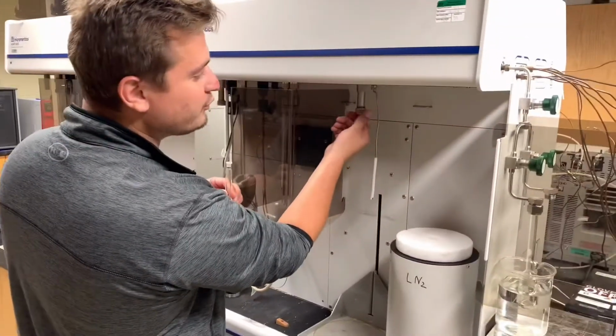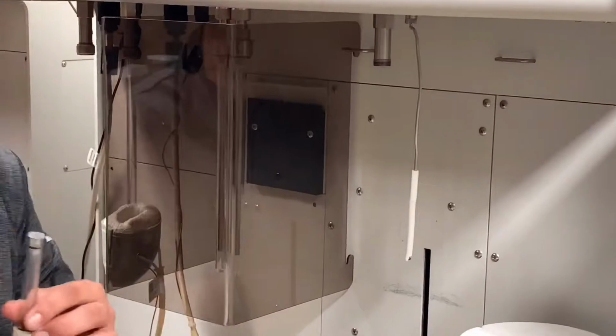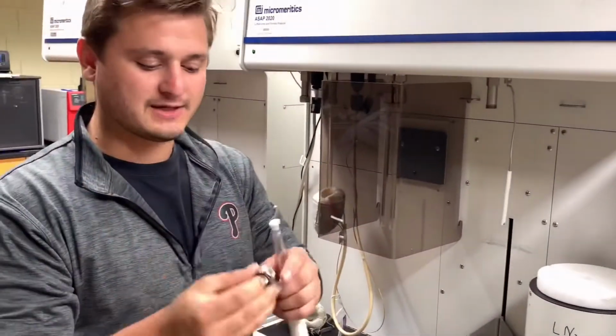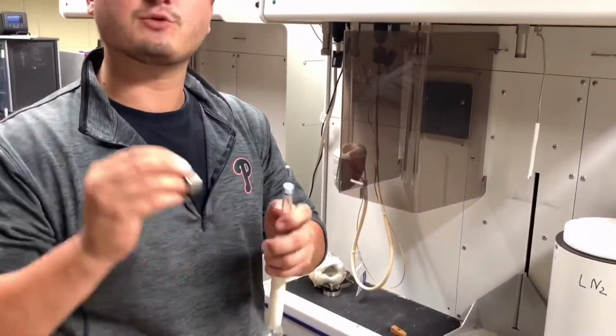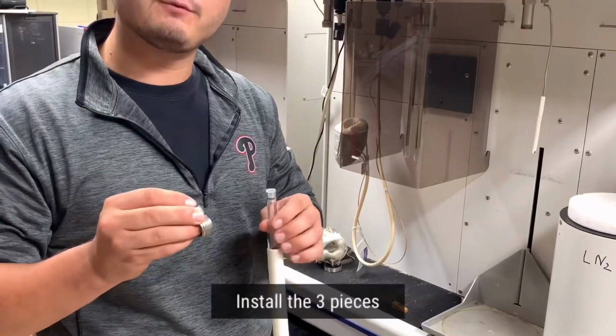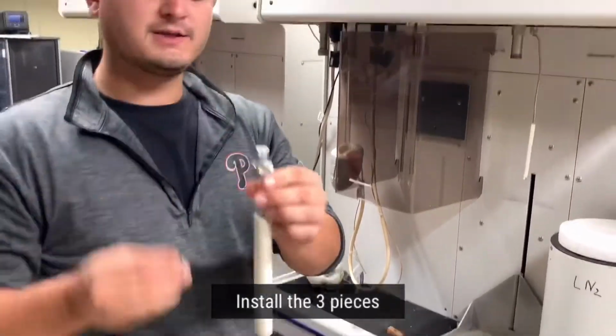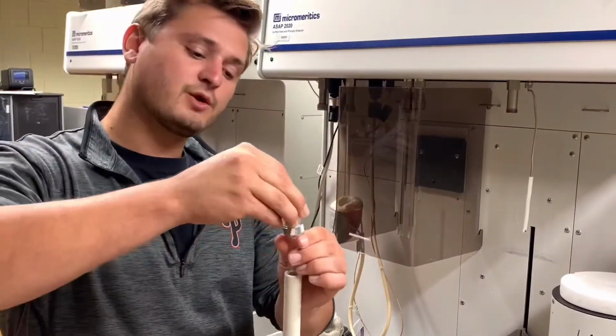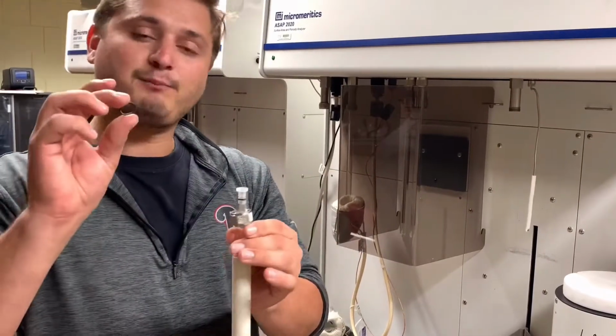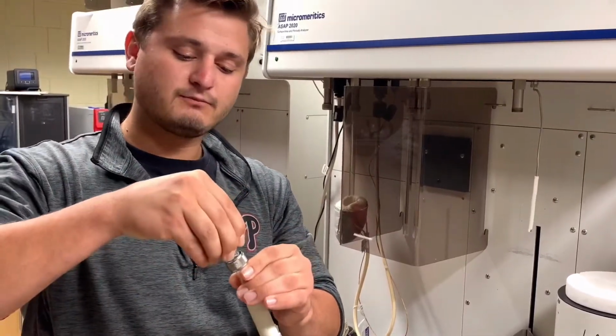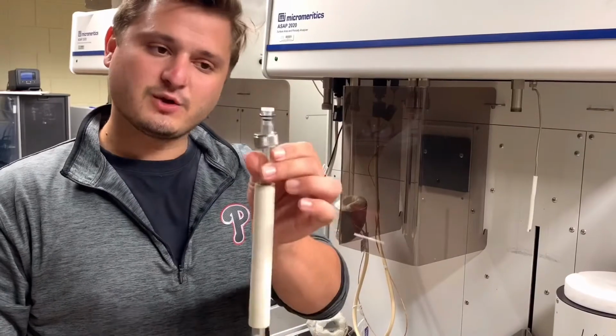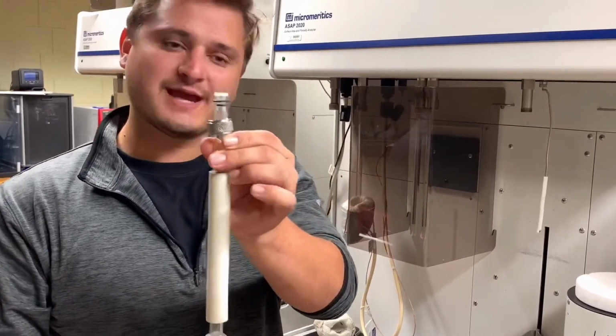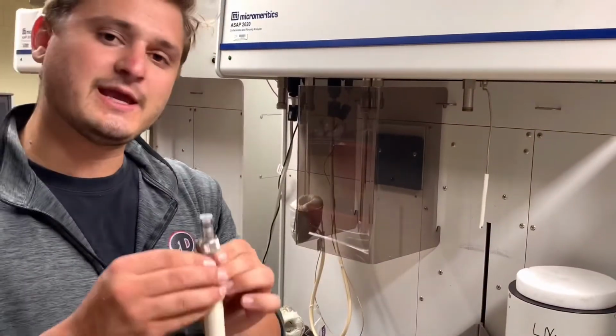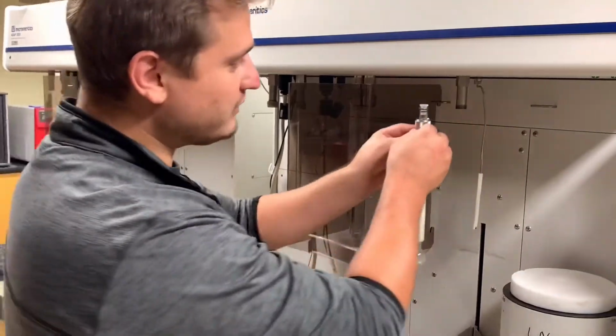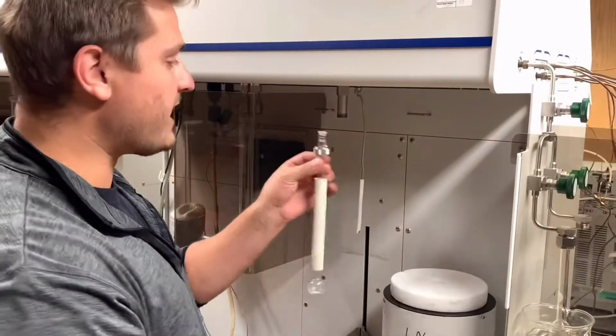You will remove the 3-piece sample connector from the instrument, as it was put there after the previous use. You will input piece 1, put on piece 2, and then piece 3, the O-ring. You will slide it down just a little bit so it's at the edge of the sample tube, just below the sample cap.